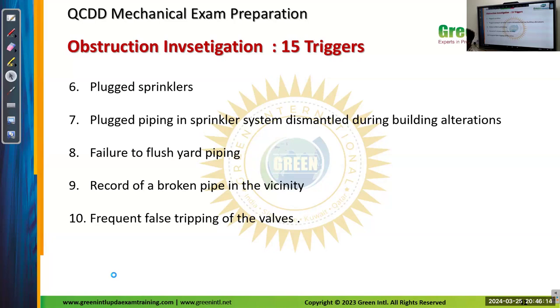Actually, as we discussed earlier in the class, if you are replacing some portion of the sprinklers, we have to do the hydro test again. The hydro test will have a pressure rating more than the sprinkler opening pressure. So at that time, we will remove the sprinklers and plug that system. For testing the branch lines and standpipe systems, we will plug the sprinklers for the entire systems. So that is called plugged sprinklers. So they plug the system and they forgot to replace that with the sprinklers. Whether there is any plugged system or not, those details will be checked.